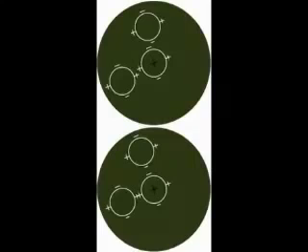You will see two plus signs between the left-hand circle and the focusing circle. To locate the axis of corneal astigmatism, turn the rotating grip knob so that the tips of the plus signs touch. If the patient has regular astigmatism — when the principal meridians are 90 degrees apart — the minus signs will align vertically. If the minus signs do not align vertically, the patient has irregular astigmatism, where the two principal meridians are not 90 degrees apart.